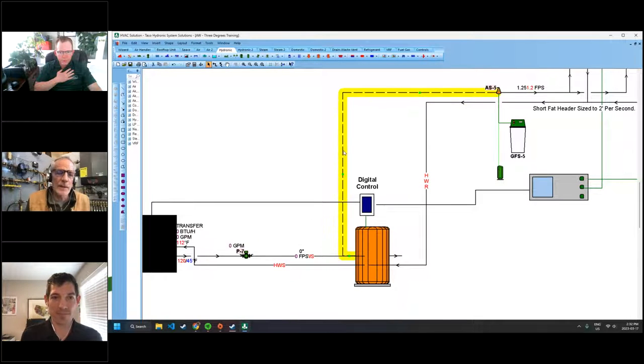Yeah, so we've been in Hydronic for 19 maybe, Max. We did an issue on buffer tanks, mainly for wood storage, but really for mod cons, anything. We talked about a 2 and a 4 pipe. The issue I have with a 4 pipe is all the water has to cross the tank every time, across the top and across the back.